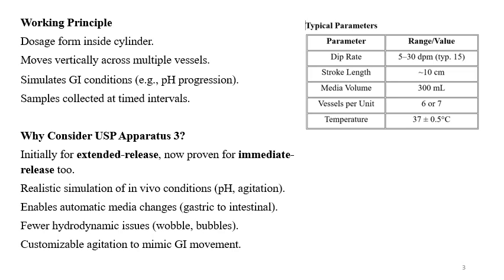Although USP1 and USP2 apparatus are widely used, USP3 was initially developed for extended release formulations and is now also used for immediate release formulations. Advantages include realistic simulation of GI conditions like pH agitation from peristaltic movement. It enables automatic media changes from gastric to intestinal, has fewer hydrodynamic issues like coning and bubbles, and can be customized to mimic GI movement.